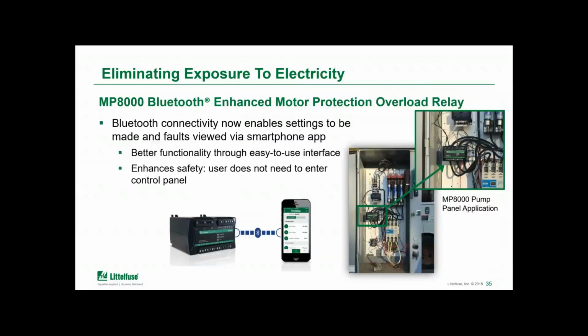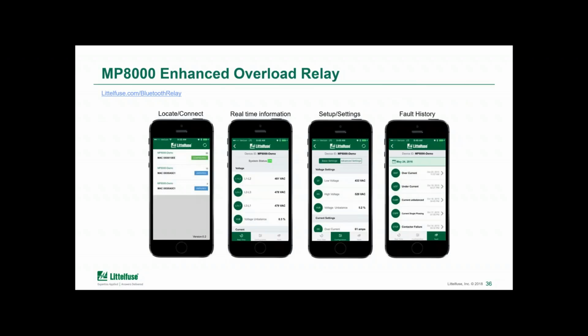And I want to show one example of an overload relay. So here the MP8000 is an overload relay enhanced with Bluetooth. And this wireless communication replaces the knobs and buttons on the face of the relay and allows you to view the faults and adjust the settings from a smartphone or a tablet, at a safer distance. So the interface would then be on the app and provides very strong functionality. So as mentioned, that really allows you to enhance safety, because now workers do not need to enter the control panel to take those readings or make those adjustments. So I just want to reiterate that because you're using an app or some other remote communications interface, that doesn't mean that you get a limited picture of what's happening with the relay.